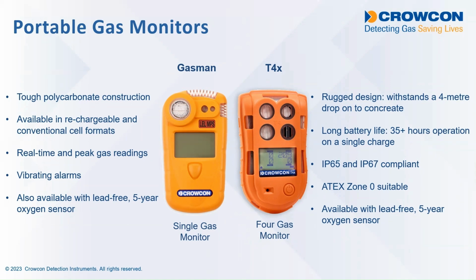And then where there are multiple gas hazards, we can have the MPS sensor in the T4X instrument, and you can also have, for example, an oxygen sensor in addition to the MPS sensor for protecting workers against the risk of oxygen depletion due to a buildup of CO2 or perhaps nitrogen leakage from nitrogen cylinders in pub cellars.